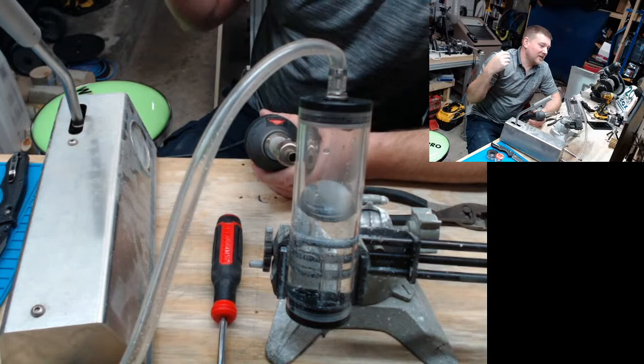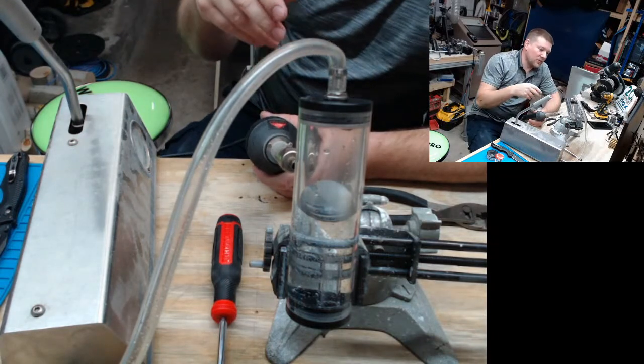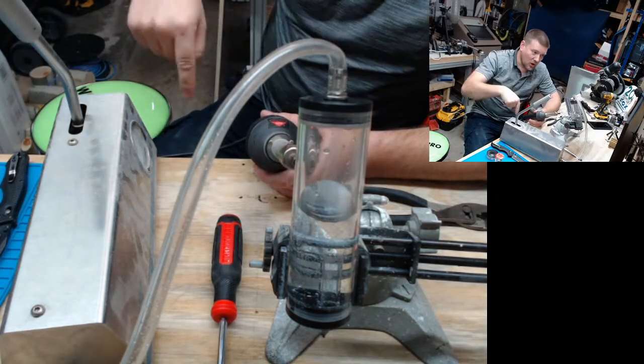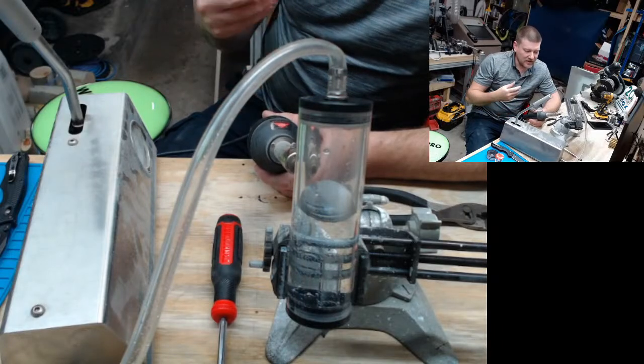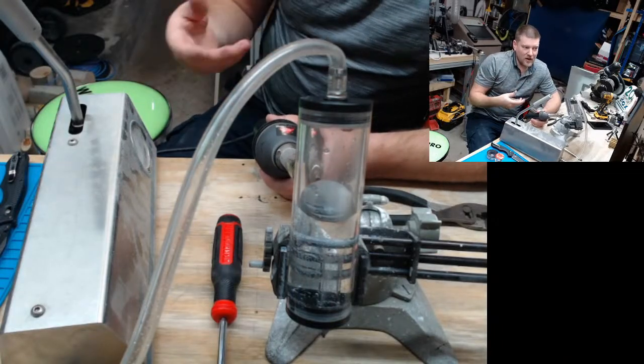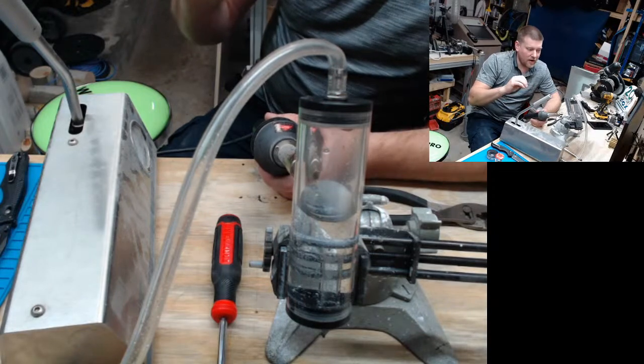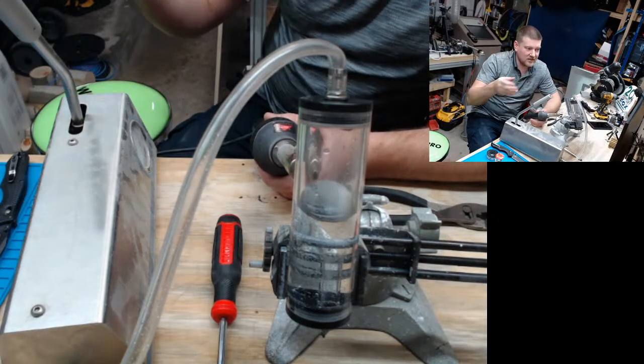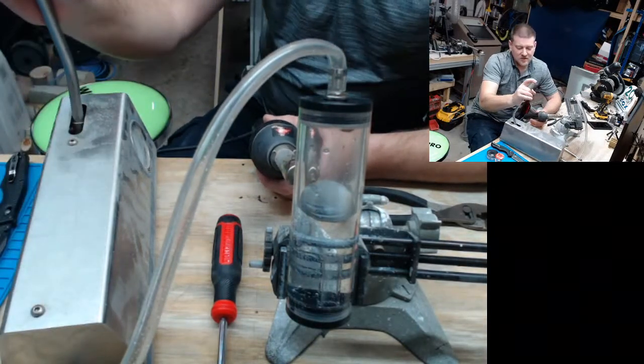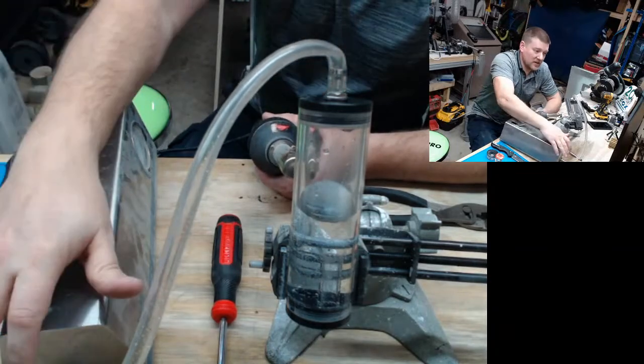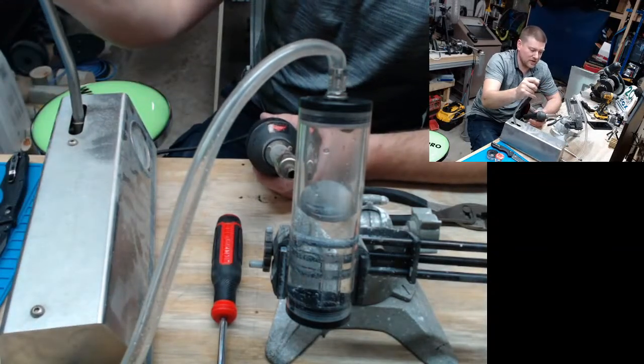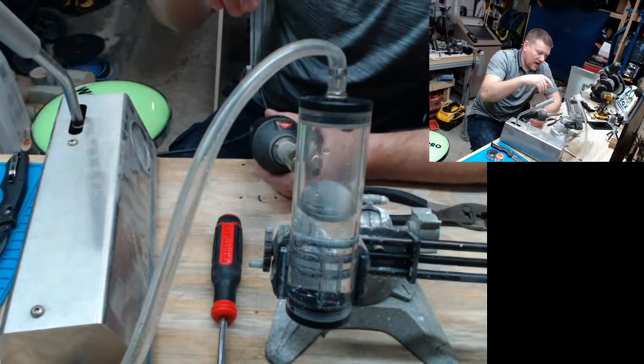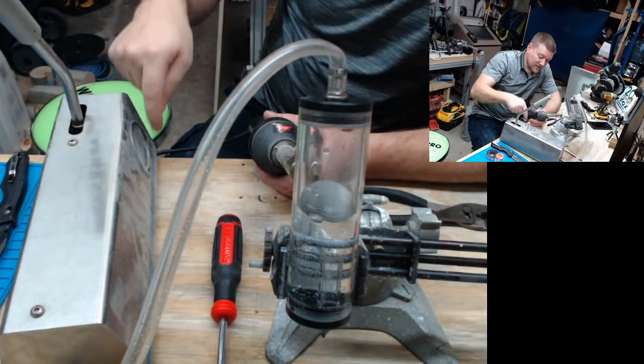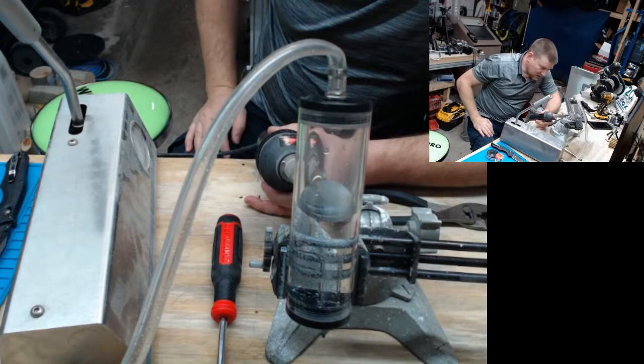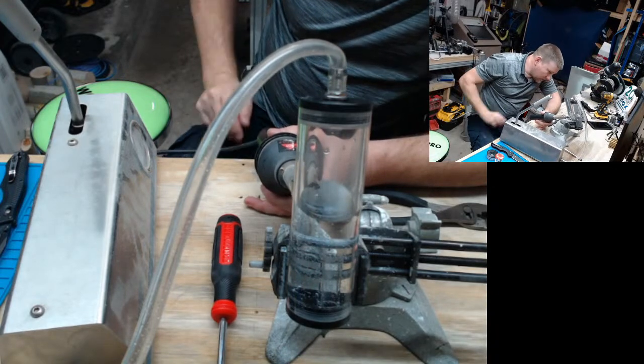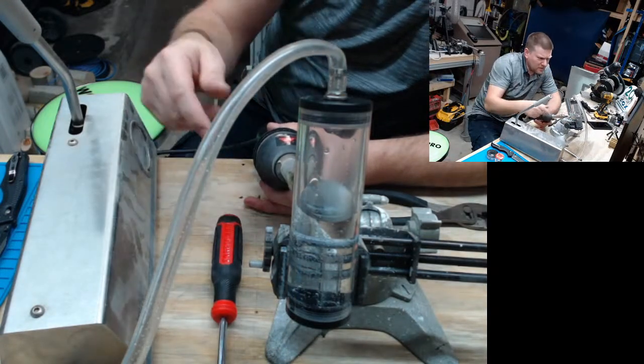We are applying a vacuum to a liquid, and we're going to make it boil at a lower temperature. So boiling is just the conversion temperature of liquid to gas. That's it. Boiling doesn't mean that it has to be hot. Boiling is just the temperature at which it converts from a liquid to a gas. And what we're doing is 30 inches of mercury. That's really low. You can see the bubbles are getting really big in there now.